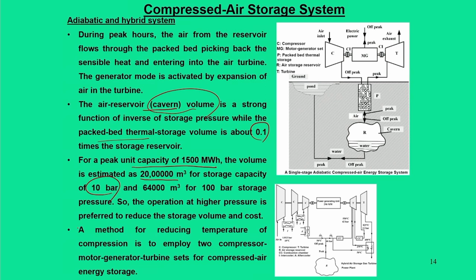Which means that if you want to store air at 10 bar pressure for producing 1500 megawatt hour energy, then you require 20 lakh meter cube storage area. So, which is huge. So, this is not a feasible option.